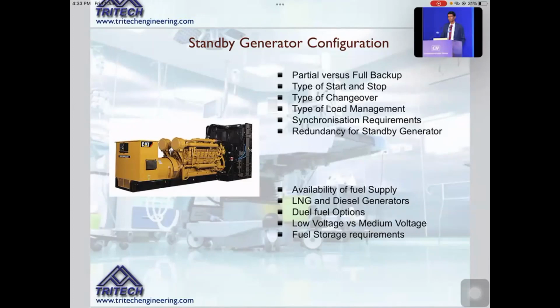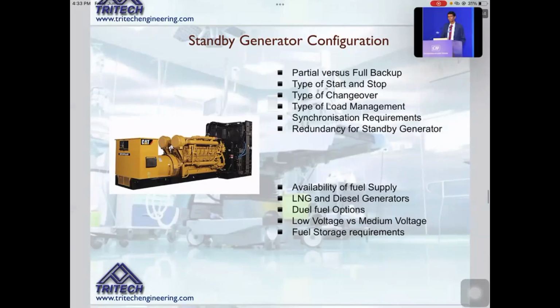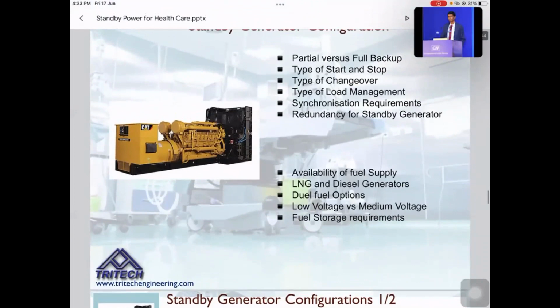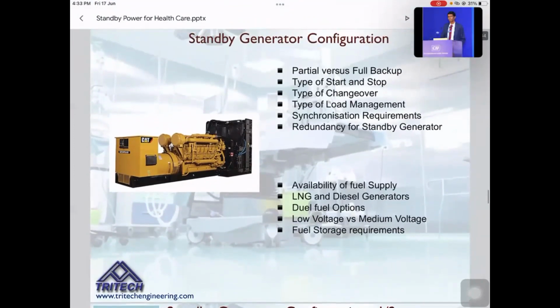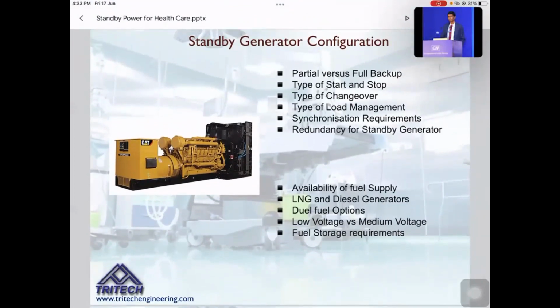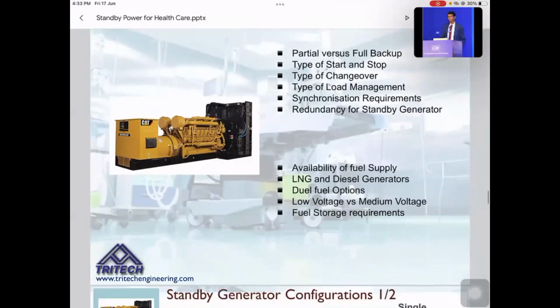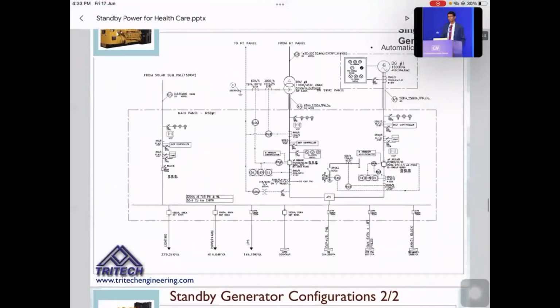Apart from the capacity or configuration of generators, there is also a multiple array of fuels now, like LNG generators, dual fuel, all those things. And looking at the fuel, you should also look at the storage requirements, because you definitely need to have at least a day's storage of fuel in the case of a healthcare facility, because your fuel supply may not be available nearby. If the fuel supply is not available nearby, it is going to affect the operations of the hospital. So fuel storage requirement is another aspect you need to look at when you're selecting this standby generator configuration.